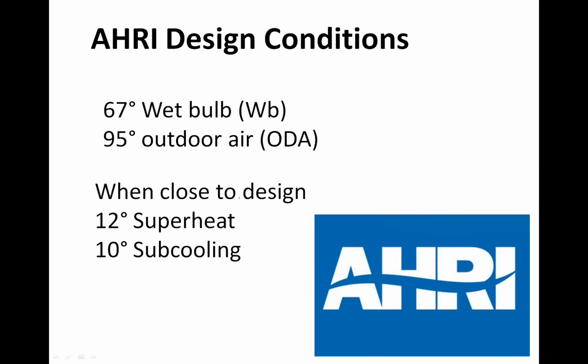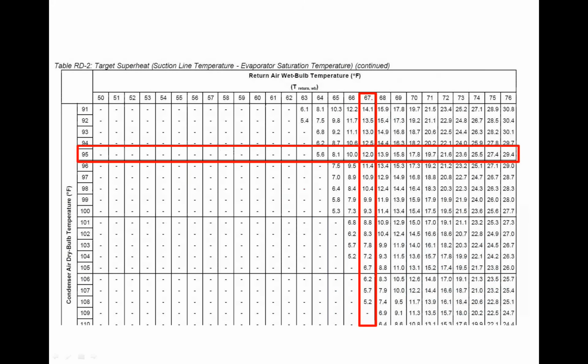So here's, if we consolidated the ARI conditions, and it's actually AHRI now, they merged with ARI. We're looking at a 67-degree wet bulb with a 95-degree outdoor air temp. When it's operating close to that design, we'll have 12 degrees of superheat and 10 degrees of subcooling. Now, I pulled up a chart here just to show you this, and I always thought this was pretty cool. This is a target superheat chart, and I'll show you where you can download this for free off of our site when you're done.